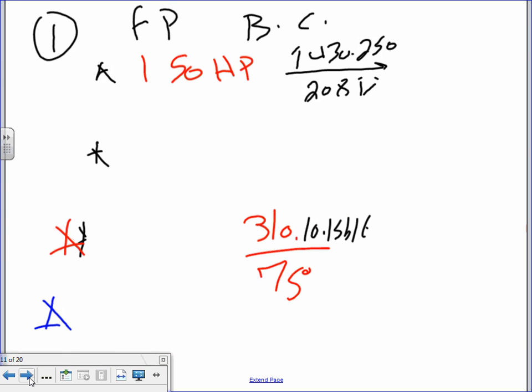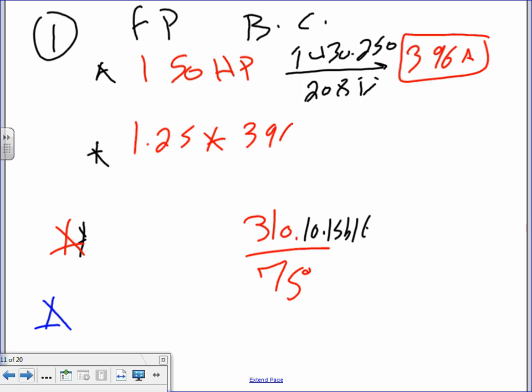So now, the first thing we need to size, Derek, my friend, is find the full load current. And if you guys do that, it's straightforward. That will be 396 amps. We have done that. So you take the 150 horsepower at 208 at Table 430.250. That'll get you 396. Straightforward. Then you multiply the 1.25 continuous load multiplied by 396. That will get you a healthy 495 amps. 495 amps. Cool?